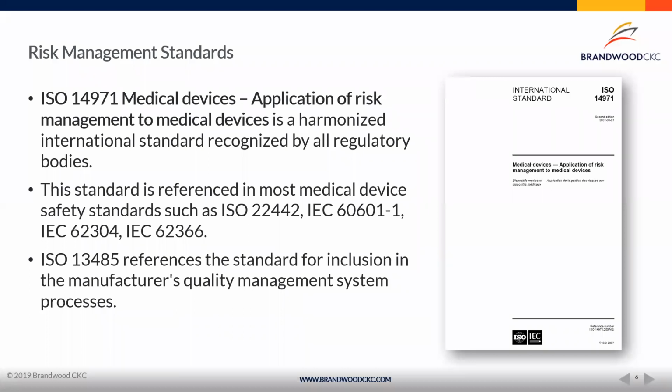And the fact that there's one playbook that we can all work off of to meet the requirements for risk management, and that's ISO 14971, is a good thing here, because that means we don't have to do separate things for every regulatory jurisdiction. We need to focus on meeting and complying to ISO 14971. And by doing that, we can then make all of our regulatory submissions appropriate for the jurisdictions that they're going to.